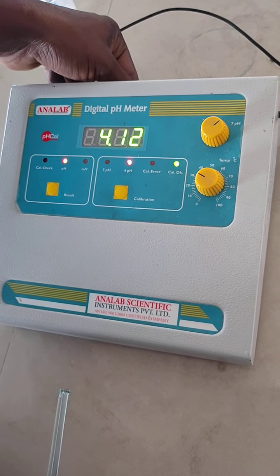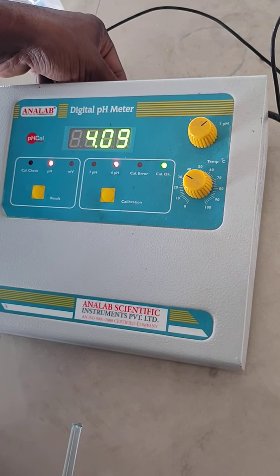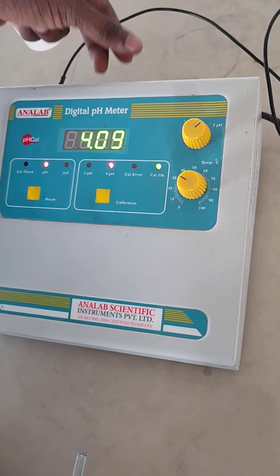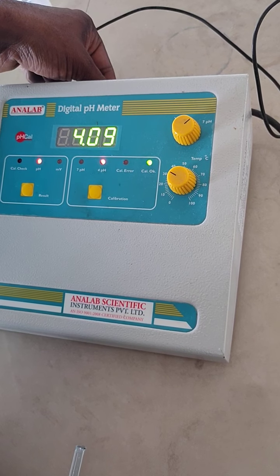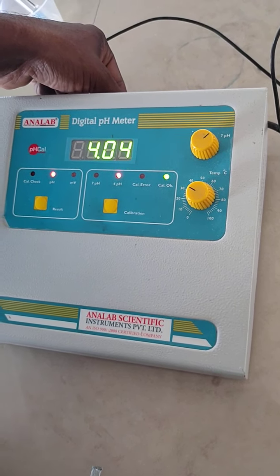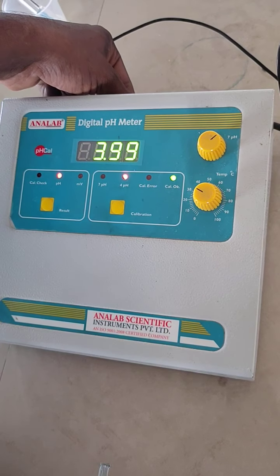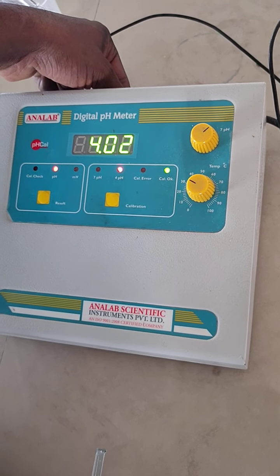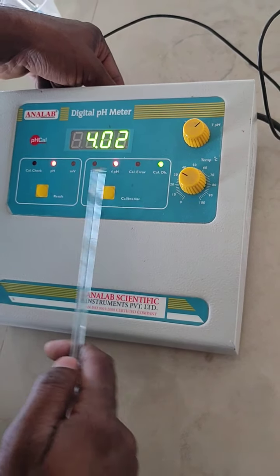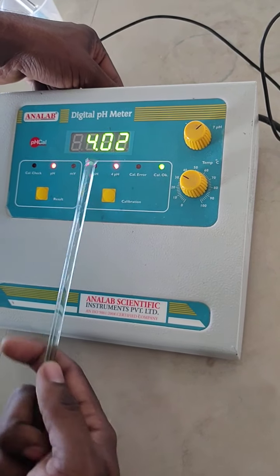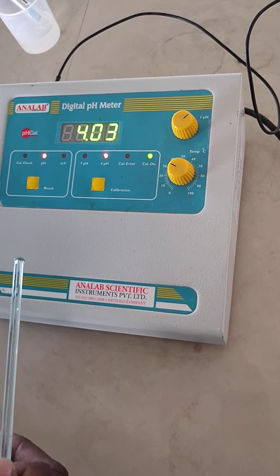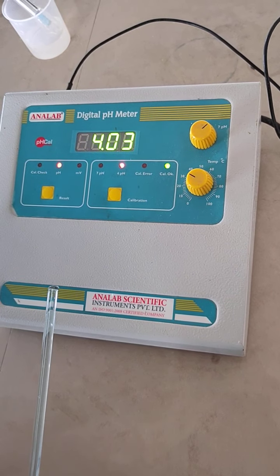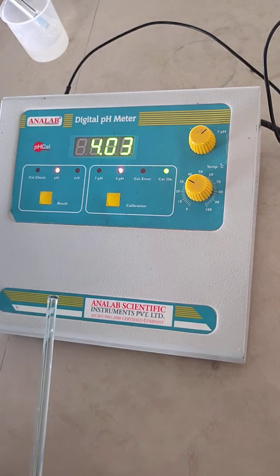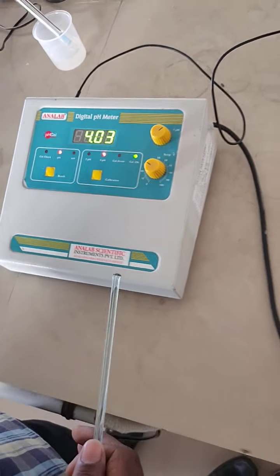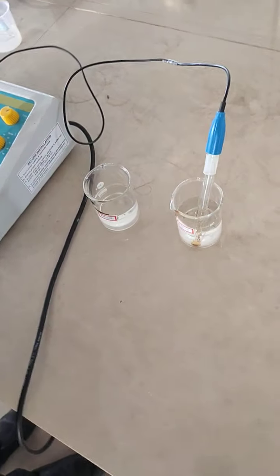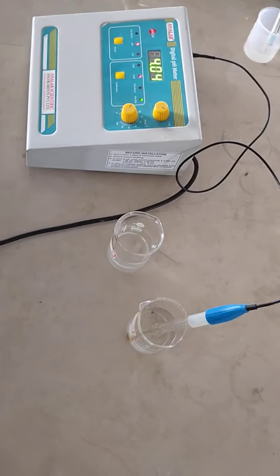So if you want to change the value, if you want to adjust this reading correctly, then slightly rotate the button in the back side. So then exactly it may show 4.02. So plus or minus 1 error is there. So no need to consider it. So then wait for 2 to 3 minutes because it reads the value of 4. Okay, now the calibration part is over.